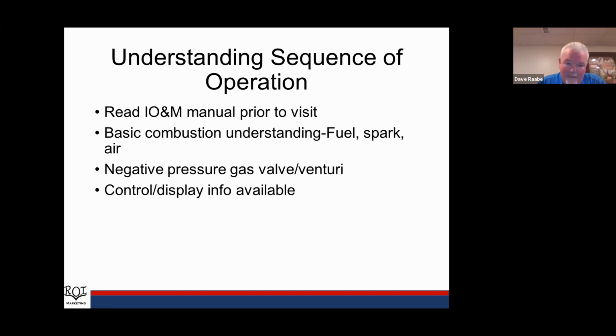The other thing you want to do is have a good understanding of how to get into the control on this boiler. At US Boiler, we use the same control and display on all of our condensing boilers. In fact, we use the same passcode to get into the installer menu on all of our boilers, which is 86. But there's an awful lot of information available through that display without putting the passcode in. Simply going to the status menu or the details menu from the very first screen allows you to get in and see all of the temperatures at any of our sensors.